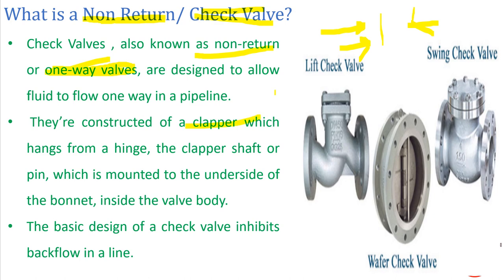These valves are basically constructed of a clapper or a plate which is hinged at the top. When the flow of fluid strikes this plate, the plate gradually opens, and when backflow strikes from another direction, the plate closes. These valves are basically used in pump lines, compressors, and pipelines where you don't want your fluid to come back — to prevent equipment damage. The basic design of a check valve inhibits backflow in a line.